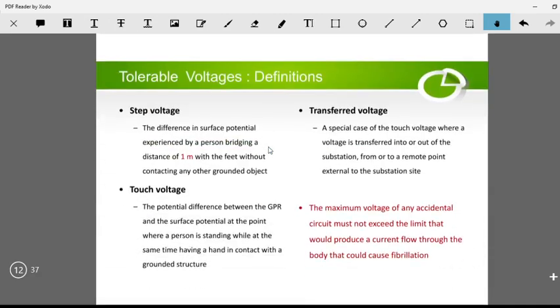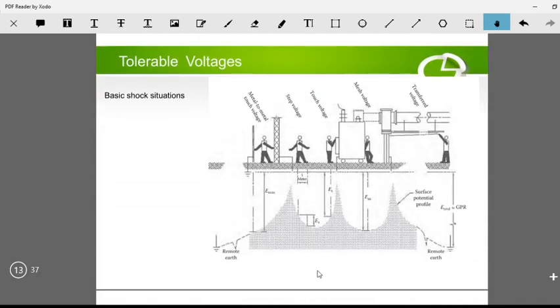In the substation you have equipment and transmission lines creating electrical and magnetic fields, which create this ground potential. But far away from the substation, you have a normal, typical earth—this is the remote earth—whose resistance you can think of as zero potential.